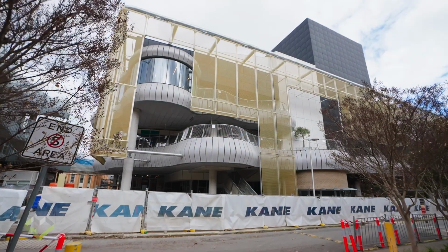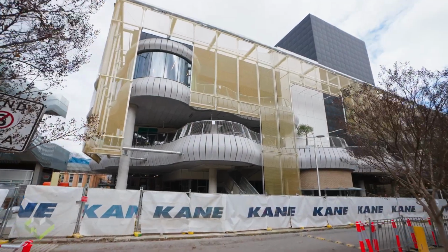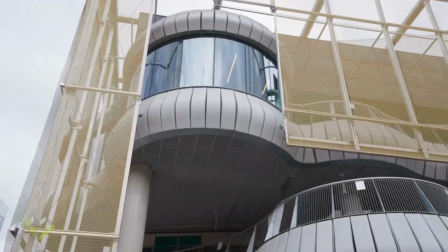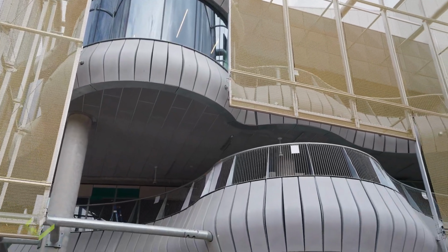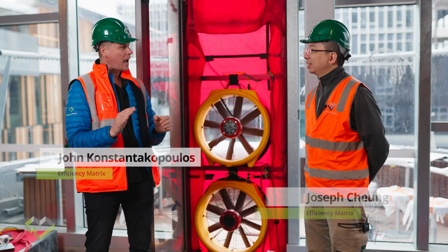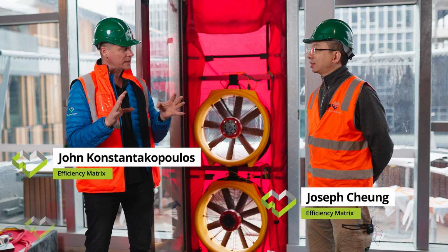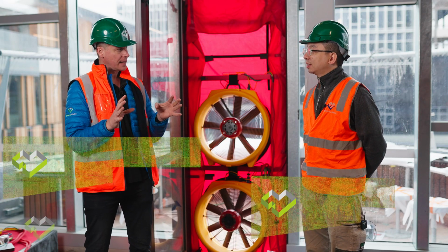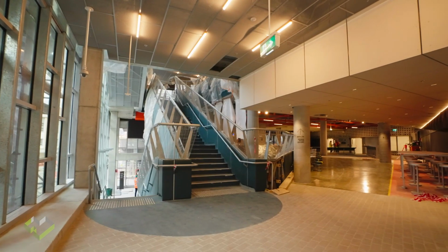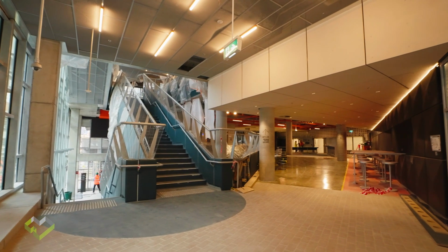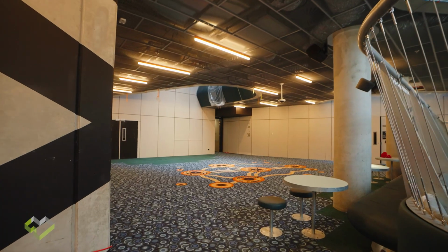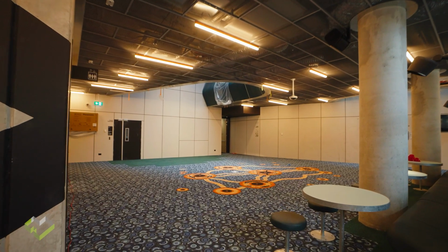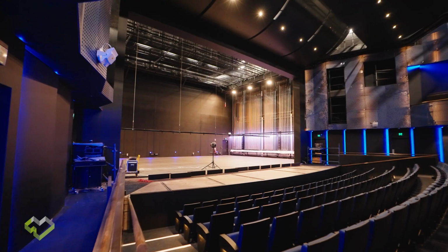Here we are, Joseph. We're about to do a large building test on a building at Melbourne University, the Cultural and Arts Building. I think a lot of people ask what an air tightness test is, and at the end of the day, a lot of people understand air changes an hour at an elevated pressure of 50 Pascal, which is roughly 32 km/h winds. But today we're testing for a permeability rate.